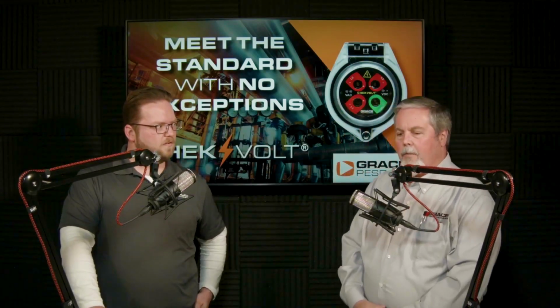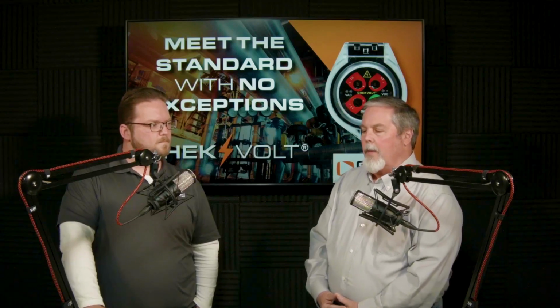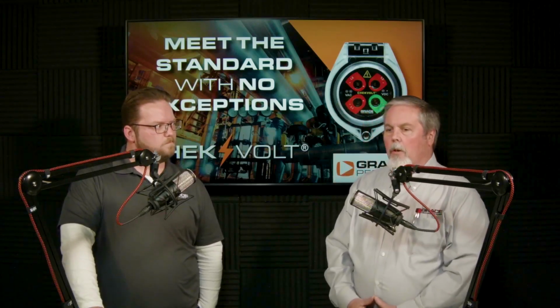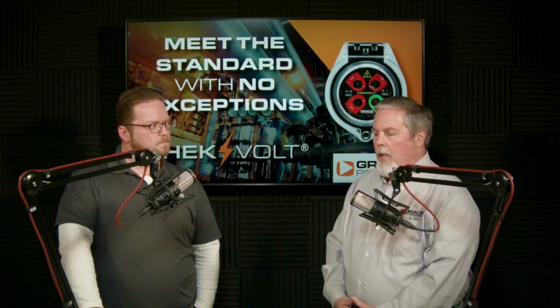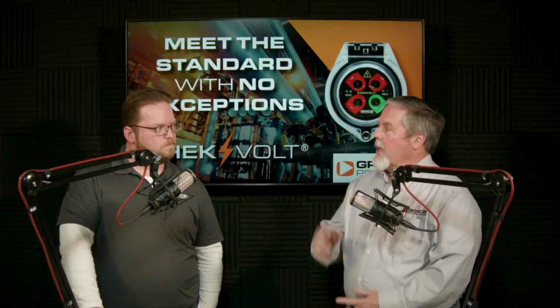Correct. So an AVT listed to 1436 was put into the UL 1436 area because it didn't necessarily meet the standard under UL 61010, which all your safety and electrical measurement devices are tested to. And the UL 1436 was created for the AVT, which is a push to test device, because it's testing your absence of voltage.